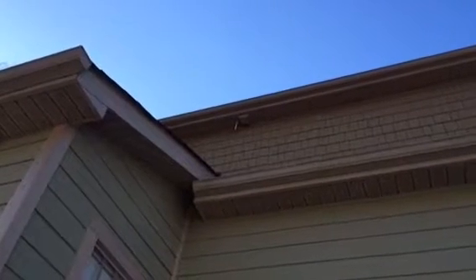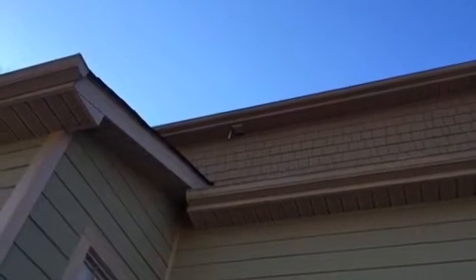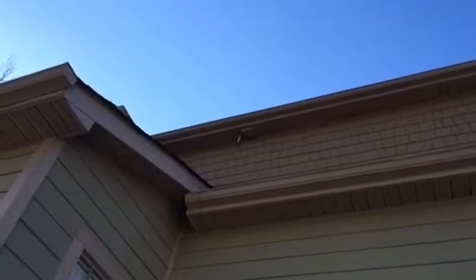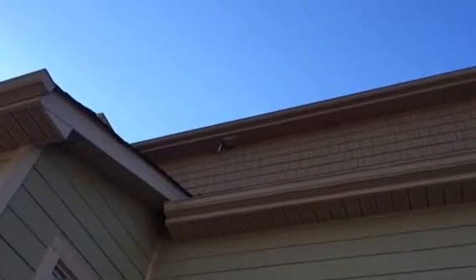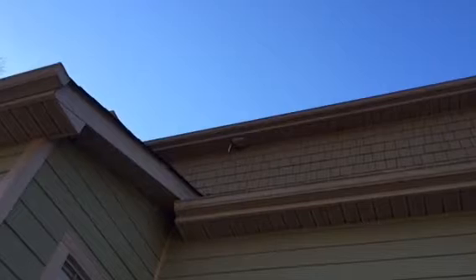There is much discussion about whether a secondary drain is needed if you have a float switch. There is no drain needed for a crawl space, or a secondary drain or drain pan for that matter. You can see a little stub coming out the soffit. That is the secondary drain or the drain pan drain.